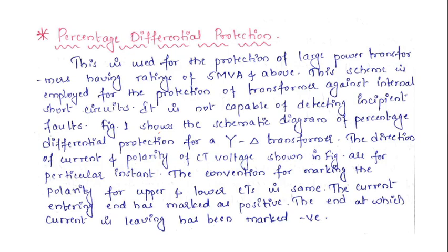Now we'll move on to the protective scheme which is employed for the transformer, known as percentage differential protection. This is used for the protection of large power transformers having a rating of 5 MVA and above. So for large transformers of rating 5 MVA and above, the percentage differential protection system is used.